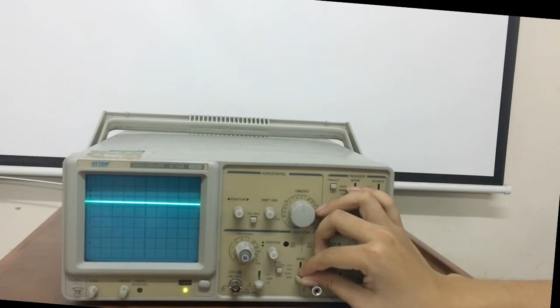Then the push-in state of channel 2. Now we have here the variable. Variable is for fine adjustment of sensitivity with a factor of less than or equal to 1/2.5 of the indicated value. When in the cal position, sensitivity is calibrated to the indicated value. When this knob is pulled out, the amplifier sensitivity is multiplied by 5.